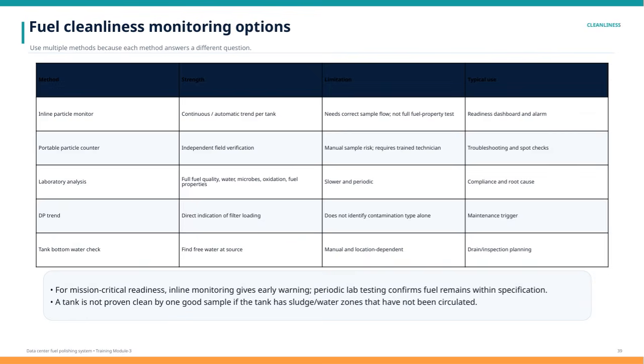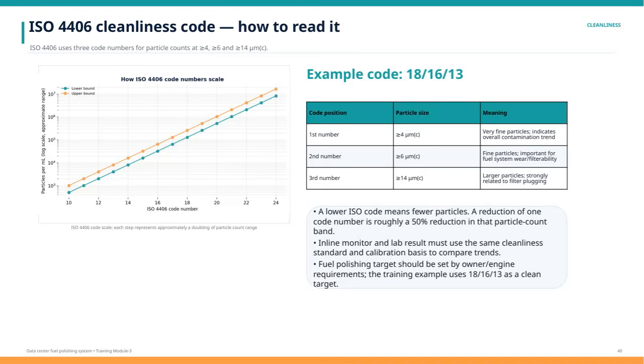For mission-critical readiness, the best approach combines inline monitoring for early warning with periodic lab testing to confirm the fuel remains within specifications. Remember, one good sample doesn't prove a tank is clean if sludge or water zones haven't been properly circulated and checked. Let's talk about the ISO 4406 Cleanliness Code and how to read it.